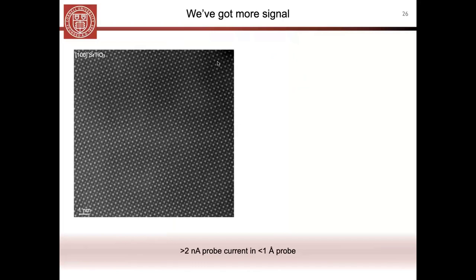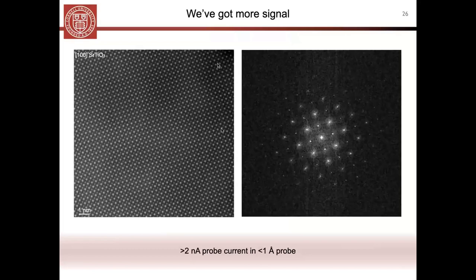The clearest way to see that is to just do it. Here's an image of strontium titanate with more than 2 nanoamps of probe current. For people less familiar with STEM, that's a lot of probe current—we typically work with things like 100 picoamps for robust materials. Anyone working on biological specimens or soft matter would be completely blown away by the idea of putting 2 nanoamps onto a sample.